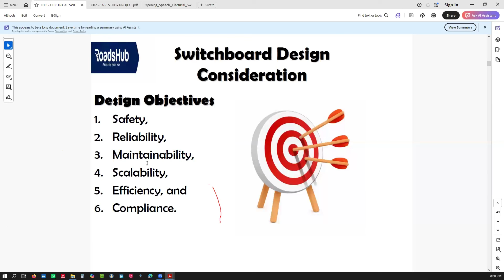So why do we actually need these systems? Because if a switchboard is responsible to run our loads, what do we need to design them? Now I bring you to the assessments, the load schedules. How much energy or how much power do you need? If you remove H from kWh, you have kilowatt, that's power. Over a period of time, it becomes energy. So how much do you need?